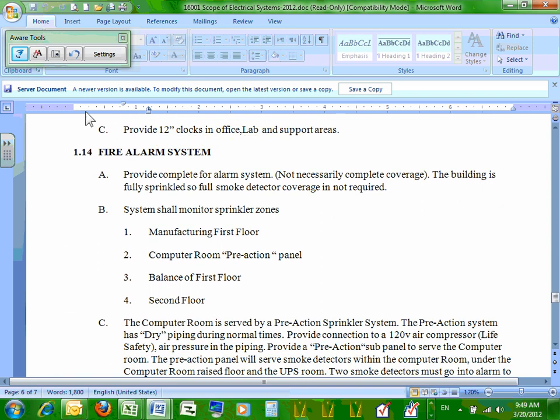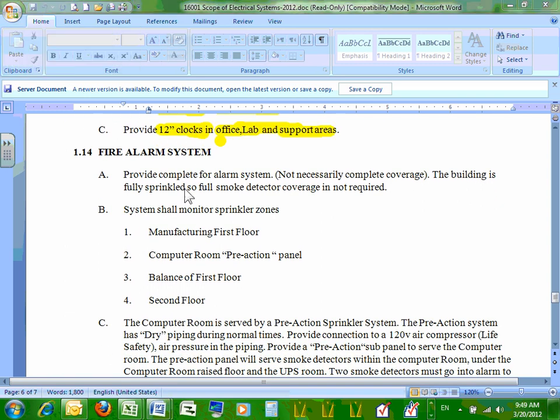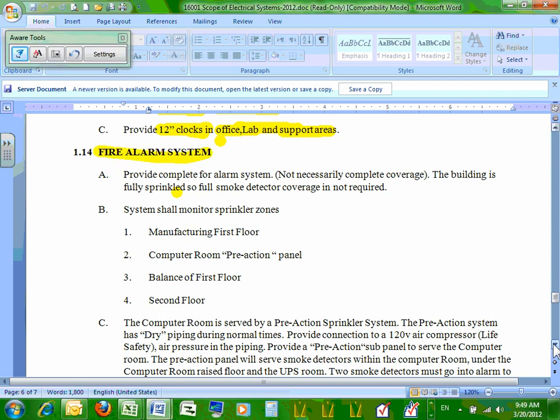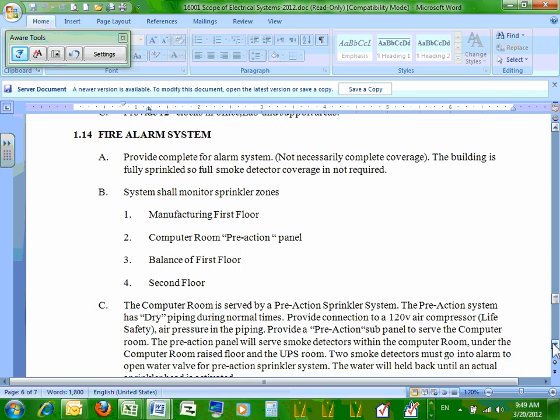We're asking for something similar to what you guys did at the commercial project. It's not code required to have complete coverage, but we just like to have you do a little bit more work. If you choose to provide detection in a building, then you have to provide code required coverage. You can't just throw in a detector here and a detector there. If you're going to put in detectors, you cross the line and you have to comply with full coverage. So we're saying, go ahead, let's provide the full coverage in our building.